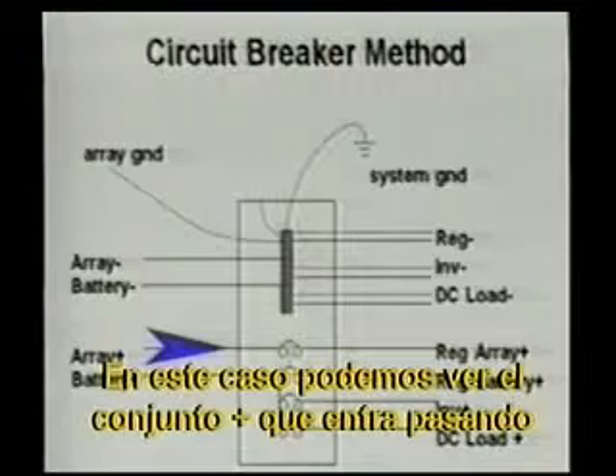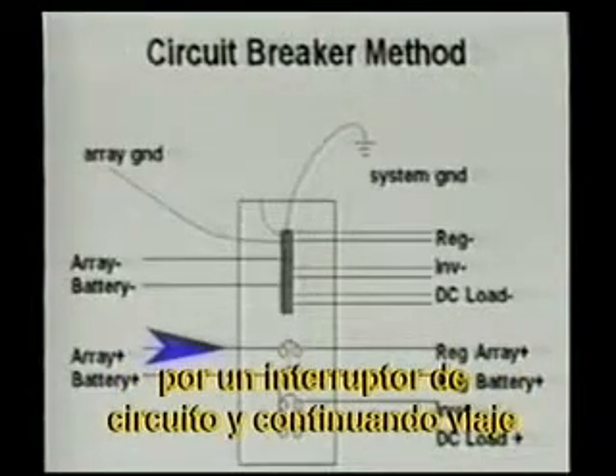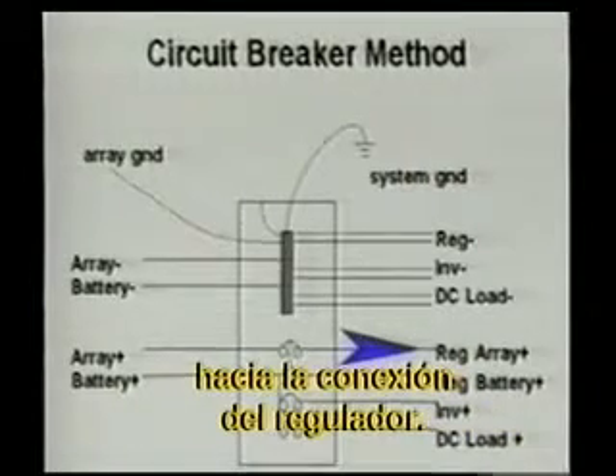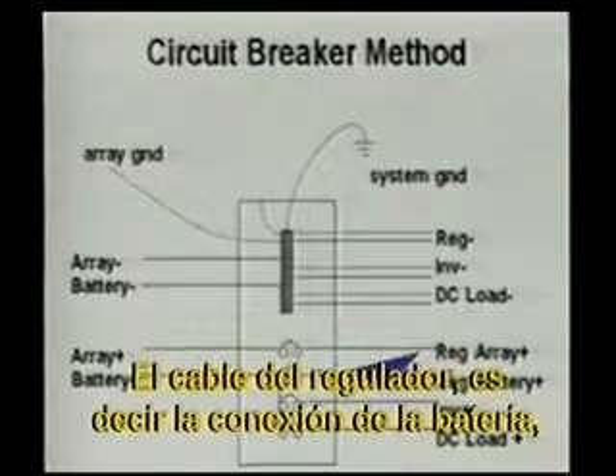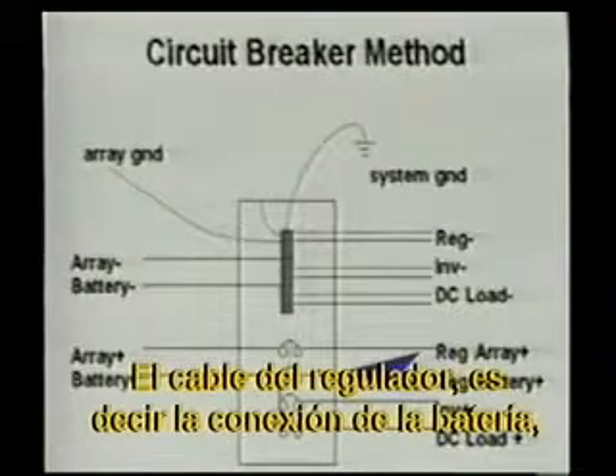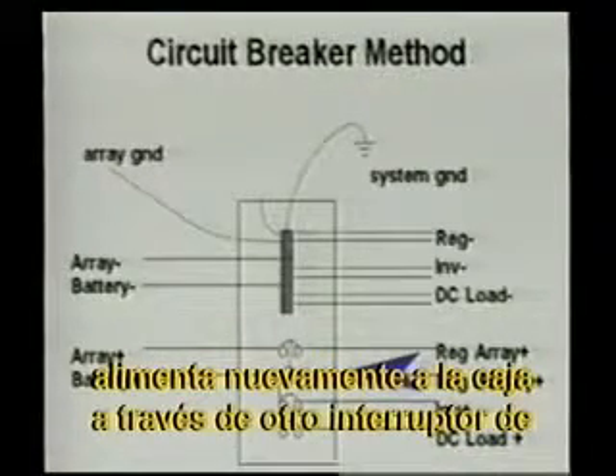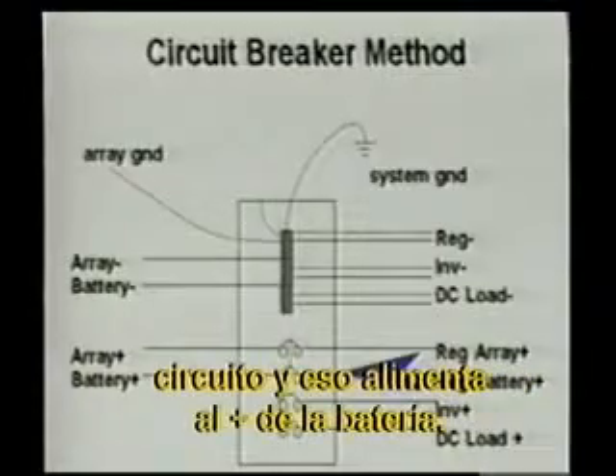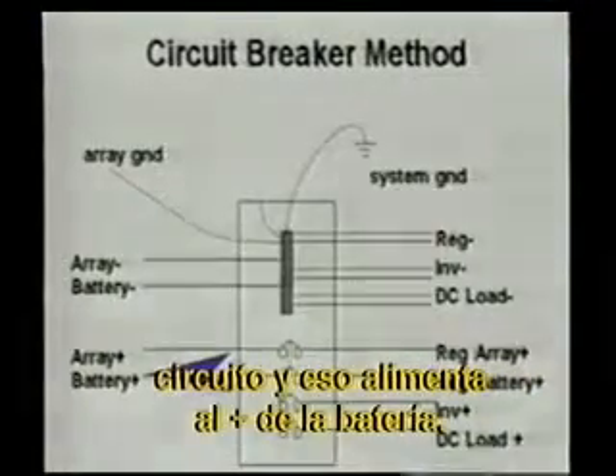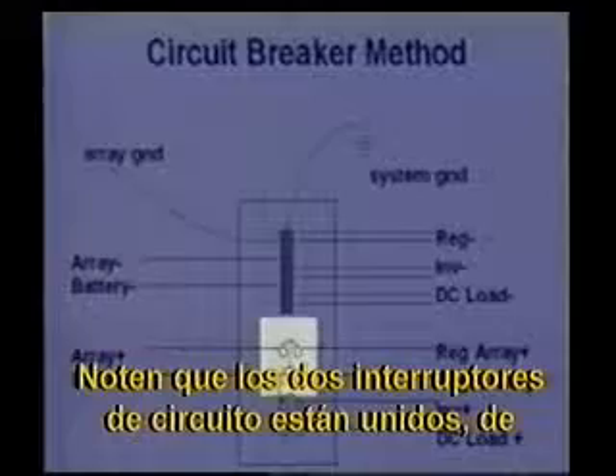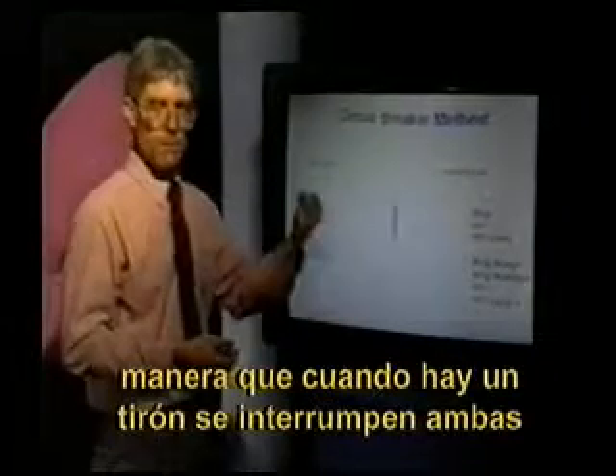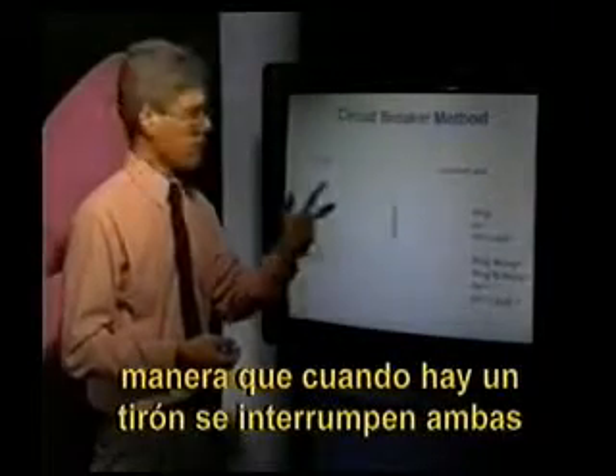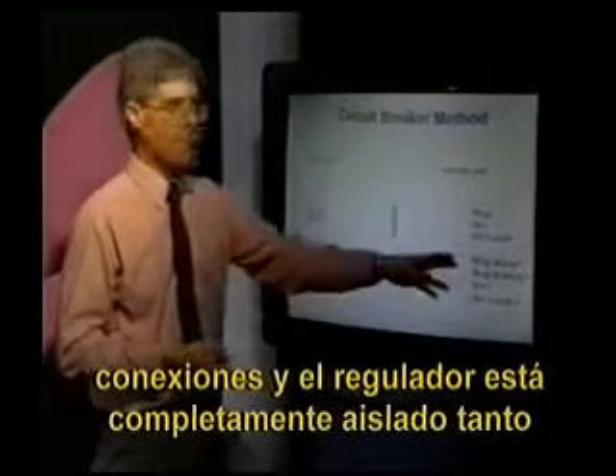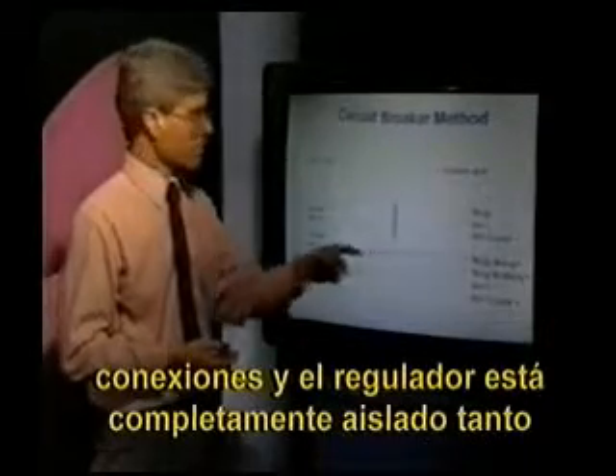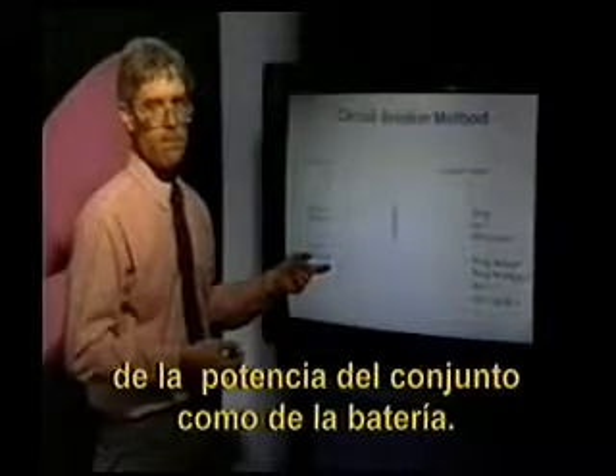In this case, we can see the array plus coming in, going through a circuit breaker, traveling on to our regulator connection. The wire from the regulator, the battery connection, feeds back into the box through another circuit breaker, and that feeds out to the battery plus. Notice that the two circuit breakers are ganged together, so that when one pull is made, both connections are broken, and the regulator is completely isolated from both the array power and the battery power.